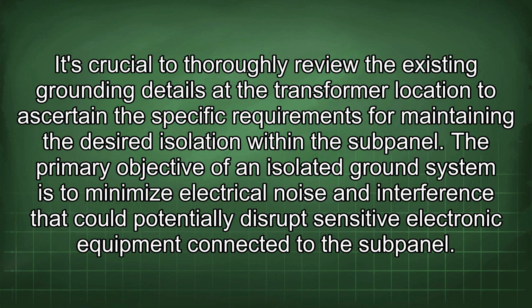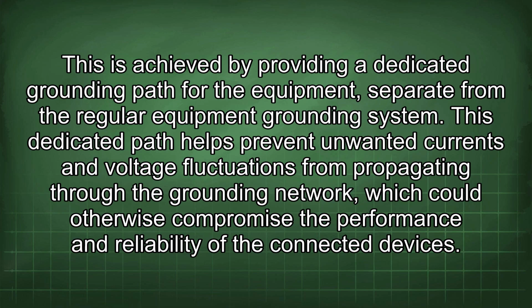The primary objective of an isolated ground system is to minimize electrical noise and interference that could potentially disrupt sensitive electronic equipment connected to the subpanel. This is achieved by providing a dedicated grounding path for the equipment, separate from the regular equipment grounding system. This dedicated path helps prevent unwanted currents and voltage fluctuations from propagating through the grounding network, which could otherwise compromise the performance and reliability of the connected devices.